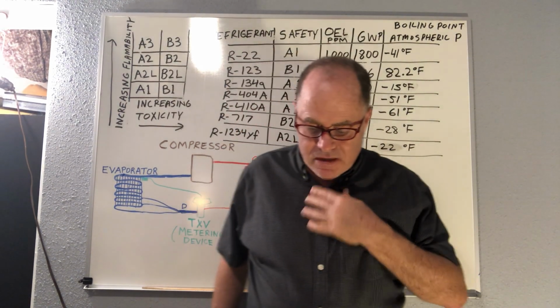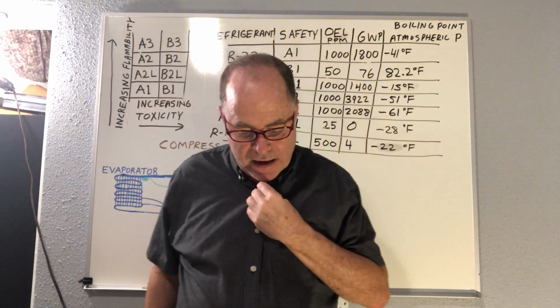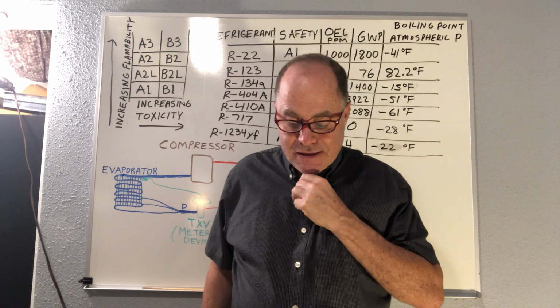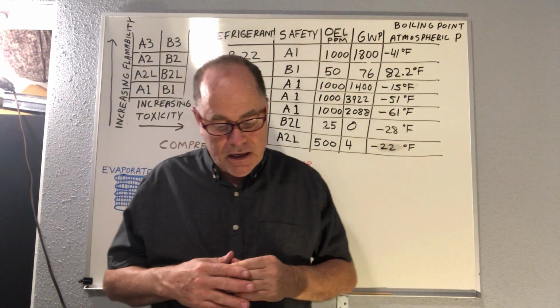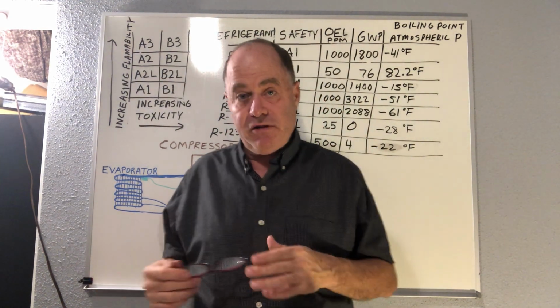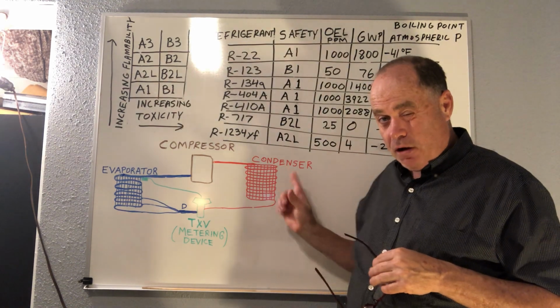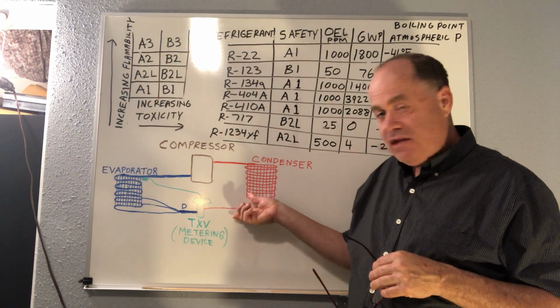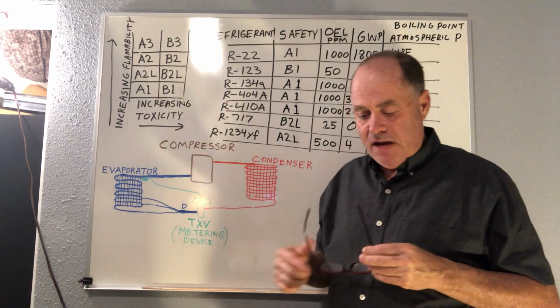Okay. Here it talks about more than 6.6 pounds of refrigerant. You need to have stop valves, suction service valve, discharge service valve, and on the outlet of the, if you have a refrigerant receiver, which would go right here, a separate vessel, not part of the condenser, a separate vessel, on the outlet of it, that's known as the king valve.